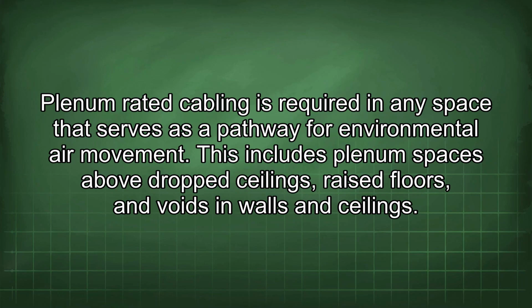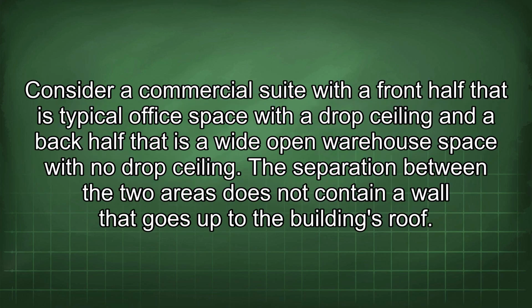Plenum-rated cabling is required in any space that serves as a pathway for environmental air movement. This includes plenum spaces above drop ceilings, raised floors, and voids in walls and ceilings. Consider a commercial suite with a front half that is typical office space with a drop ceiling and a back half that is a wide open warehouse space with no drop ceiling. The separation between the two areas does not contain a wall that goes up to the building's roof.